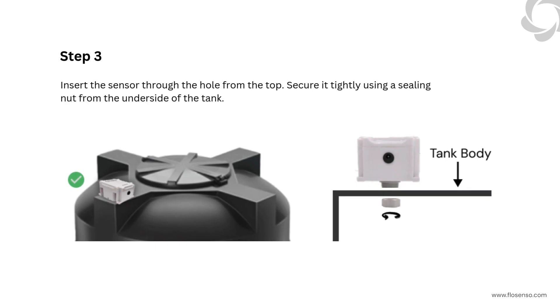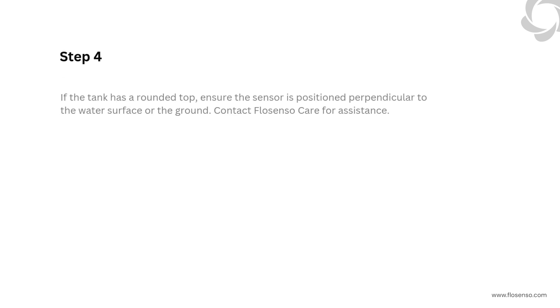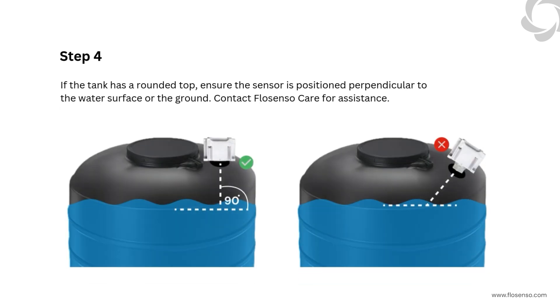Step 3: Insert the sensor through the hole from the top. Secure it tightly using a sealing nut from the underside of the tank. Step 4: If the tank has a rounded top, ensure the sensor is positioned perpendicular to the water surface or the ground. Contact Flosenso Care for assistance.